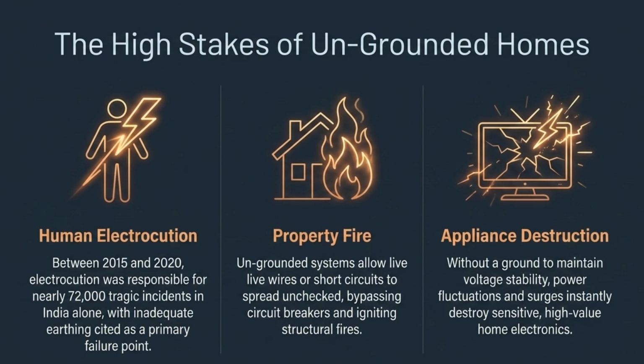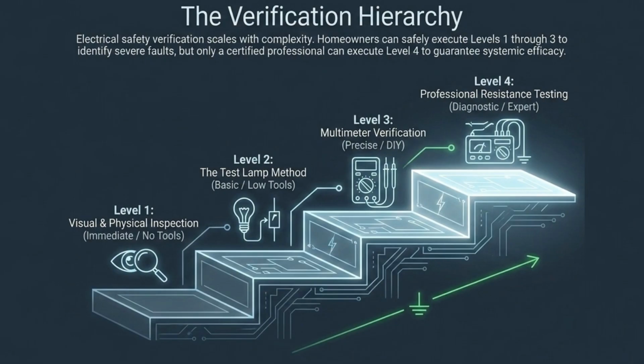The stakes are high. Without proper grounding, unchecked electrical faults can lead to human electrocution, destructive property fires, and the total loss of sensitive, high-value home electronics due to power surges. We follow a 4-level verification hierarchy. Homeowners can safely perform the first 3 levels to identify faults. However, Level 4 requires a certified professional to guarantee that your system is fully compliant and effective.